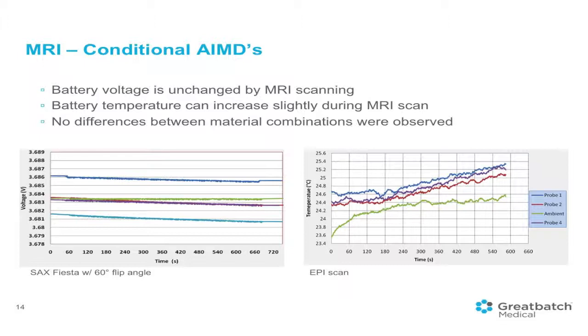And we also monitored the temperature of the battery in the MRI, and you can see that there is actually a slight rise in the temperature. And this is caused by the eddy current heating from the RF energy. But it's pretty small. It's about 1 degree Celsius, and we actually measured it, in this case, in 3 different places. And in all instances, we didn't really see much difference between the different material combinations in this test. They were all pretty similar.